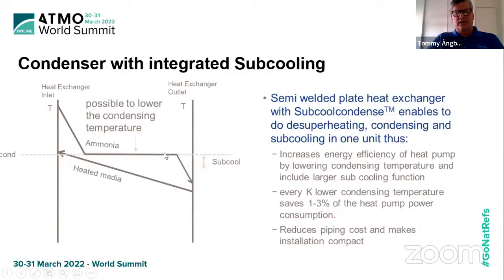And for every degree lower condensing temperature we can have, getting closer here, we can save 1 to 3% of the heat pump power consumption. So normally you would have to raise the condensing temperature quite a lot if you're not using a heat exchanger with the subcooled condenser built in.